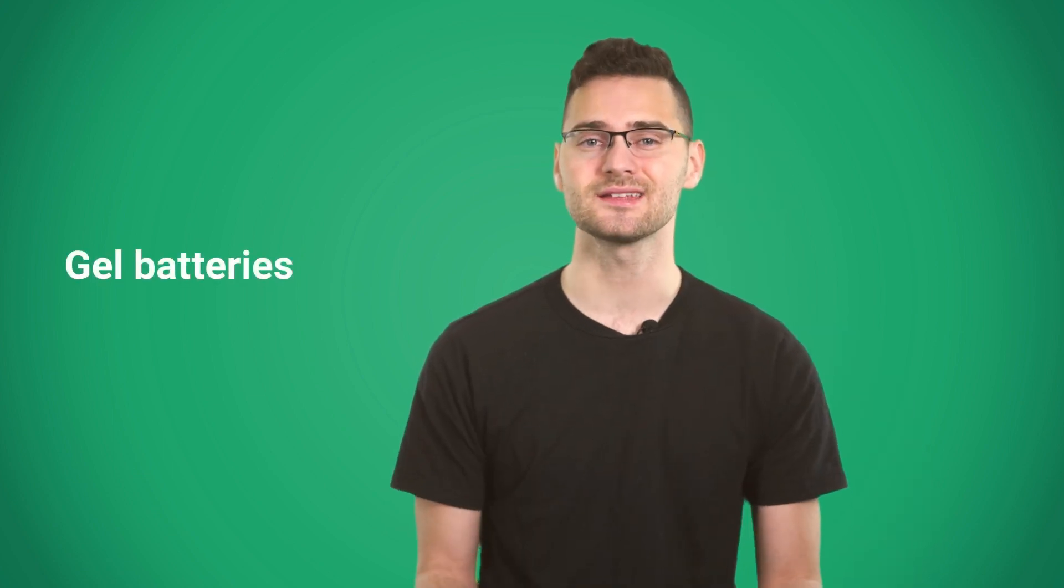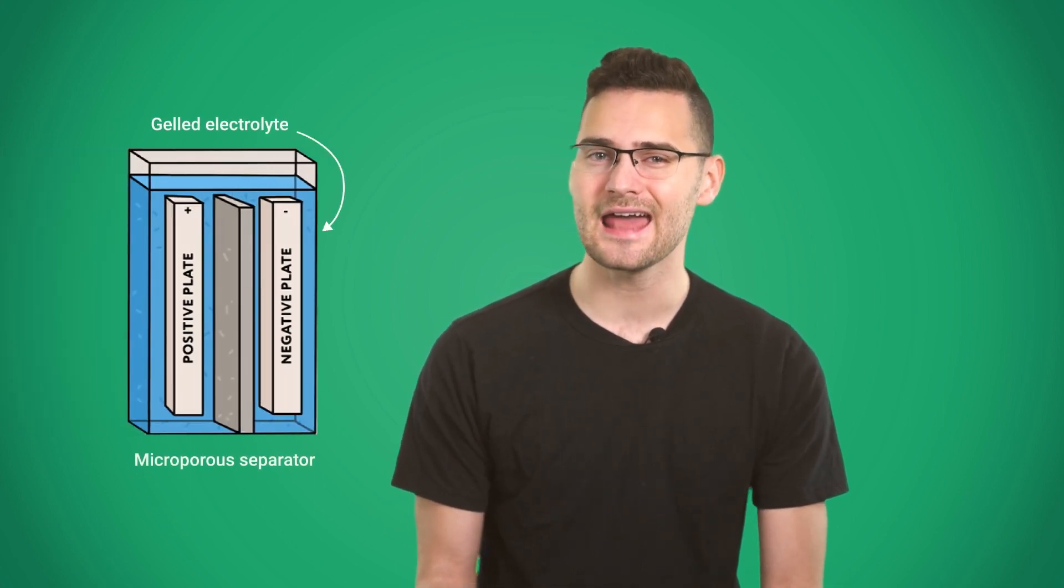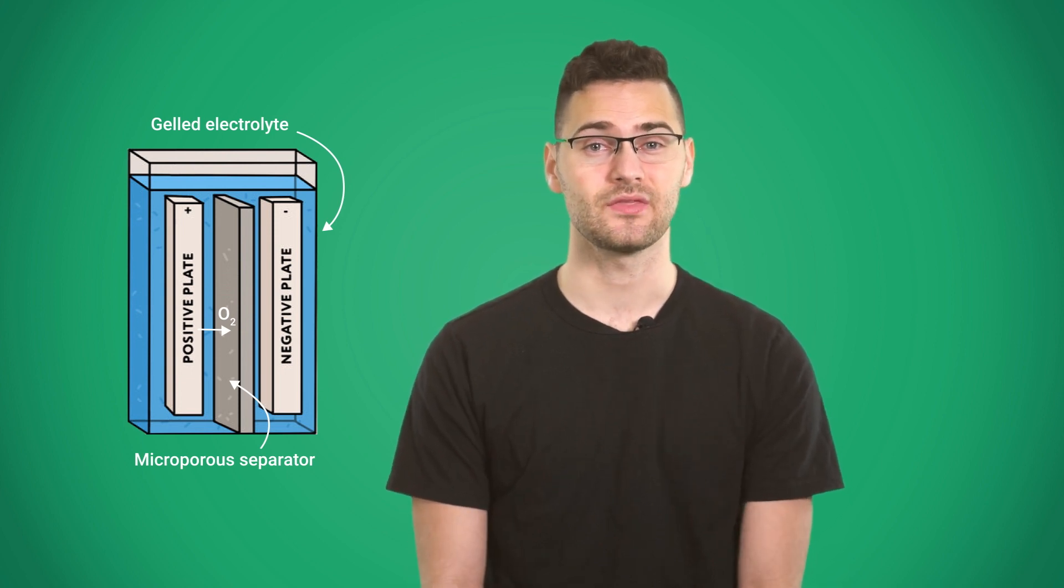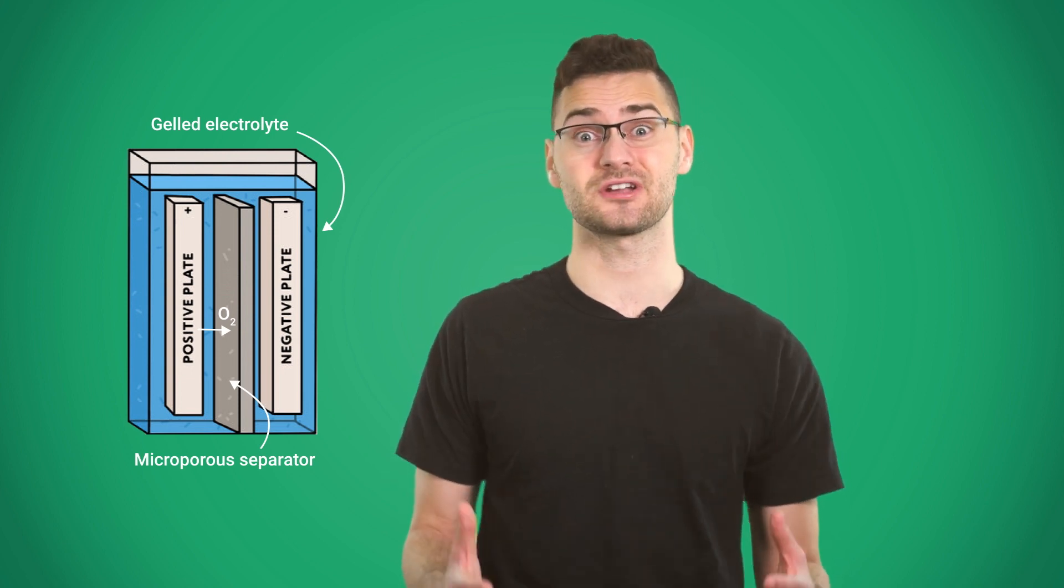Gel batteries are a second subtype of lead acid batteries. Technically, it's a wet cell battery, but a silica additive makes the electrolyte stiff, so it doesn't have the risk of spilling. They are also much better at withstanding extreme temperatures. The problem with gel batteries is their voltage sensitivity. They really don't like being overcharged. Their safe depth of discharge is slightly higher, about 75 percent.